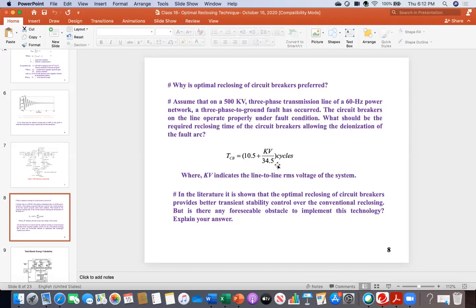So from this equation, everybody put this number 500, just 500. Keep in mind, you don't need to change into volts. This number is directly kV. Don't make that mistake. So just that 500. When it is a 500 kV system, about 25 cycles. Then tell me in seconds, how much in seconds? That is the thing. Please tell me in seconds.